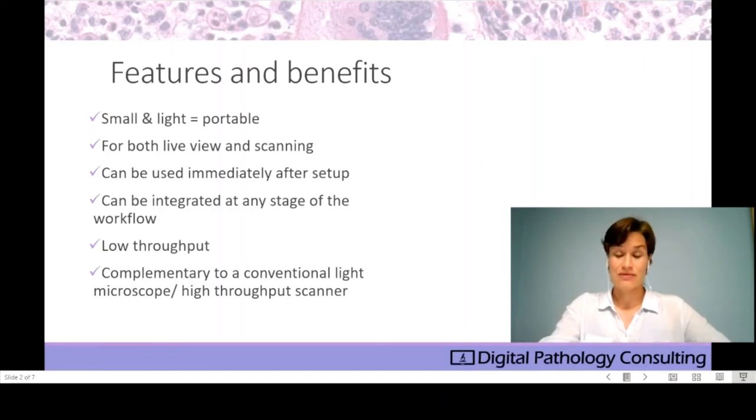It is a low throughput device. It just scans one slide at a time. So you basically put one slide at a time, like in a microscope. And it is complementary to a conventional light microscope and high throughput scanner. So if you are using a microscope for your normal work, and you just screen or review your cases under the microscope, and then you come across something that you want to scan, you take the slide, you put it into the Grundium scanning microscope. Or if you have a high throughput scanner in your institution for certain applications, but you want to just share one slide and you don't want to use the whole scanner, or you need to wait till you have enough slides to scan this particular one, it is also a complementary device.